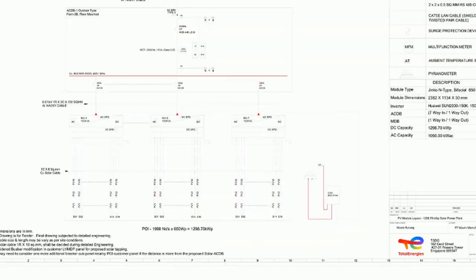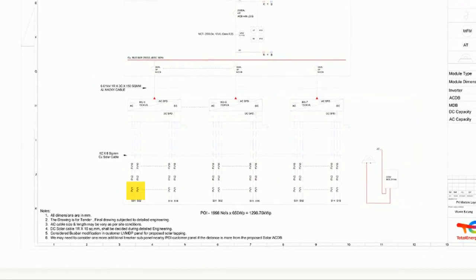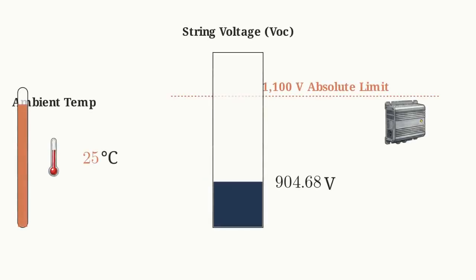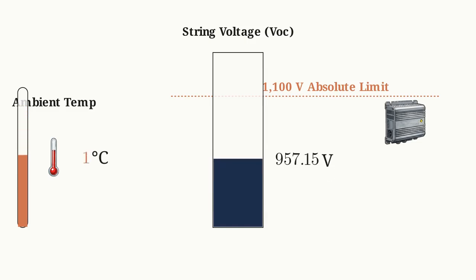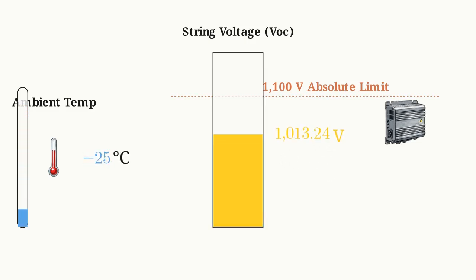This electrical single-line diagram outlines the raw scale of the DC layout. Our 1,998 photovoltaic modules are logically partitioned into 111 individual strings, with 18 modules wired in series per string. Configuring modules in series creates a specific physics hazard: voltage accumulation. As temperatures drop, solar module voltage increases, risking hardware limits during cold extremes.